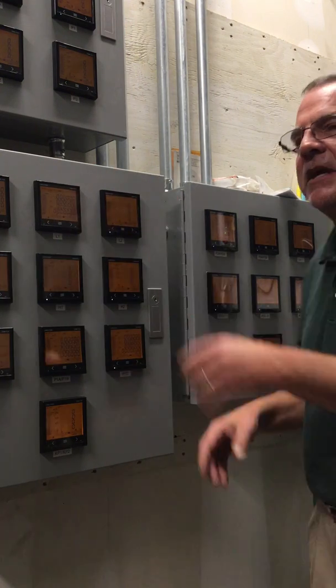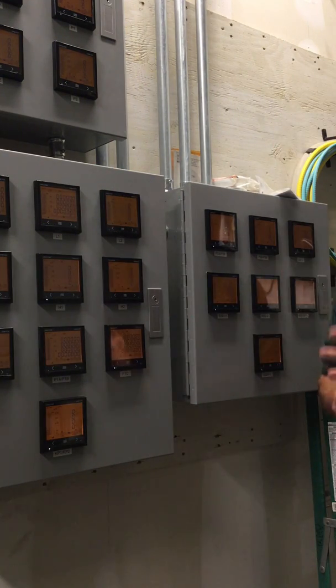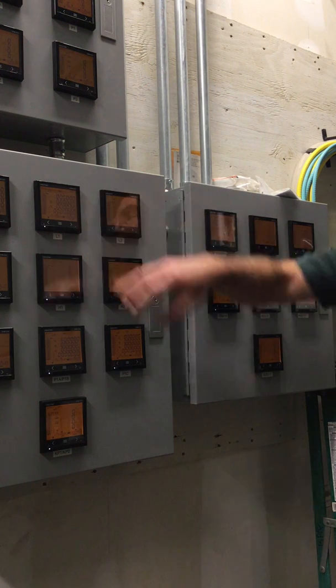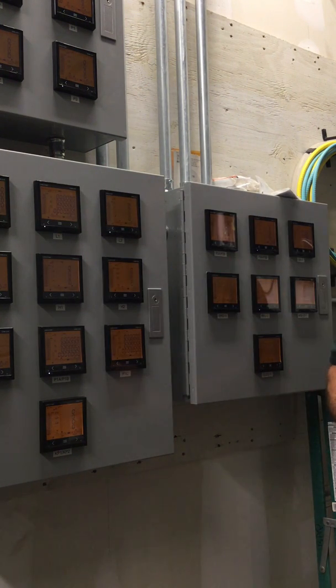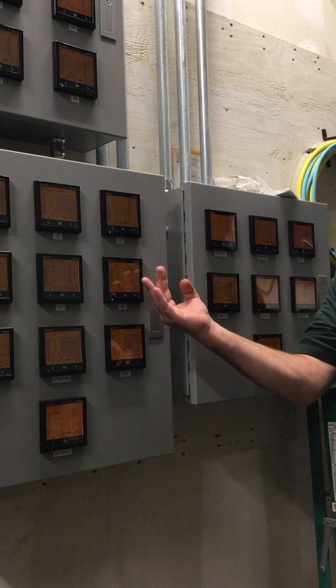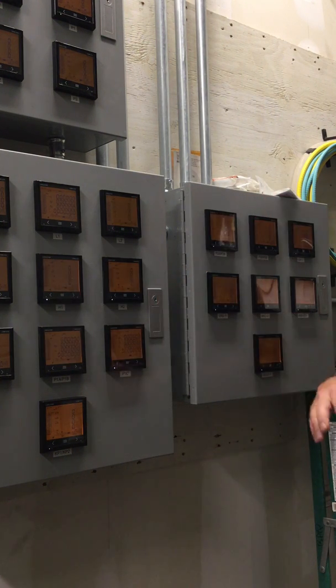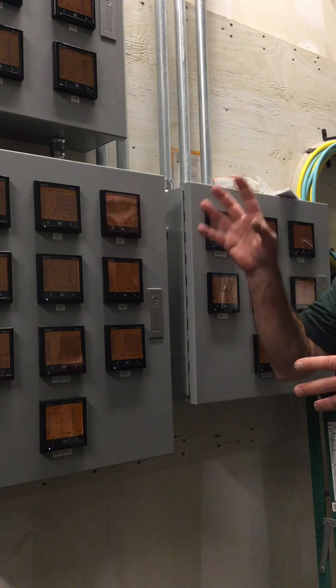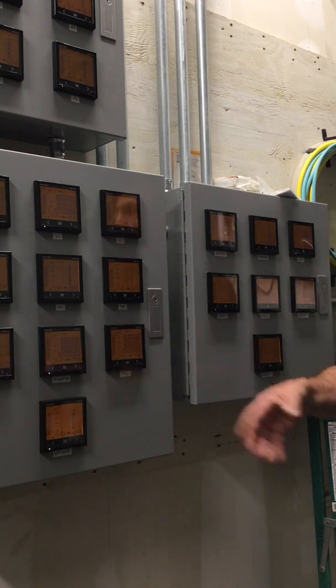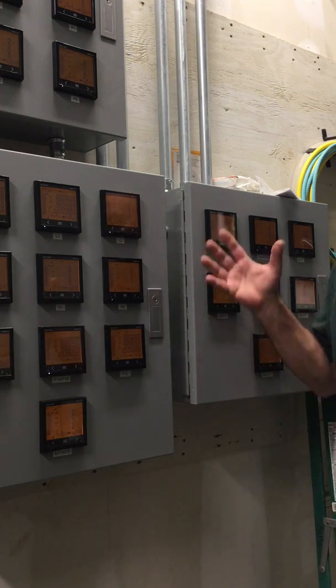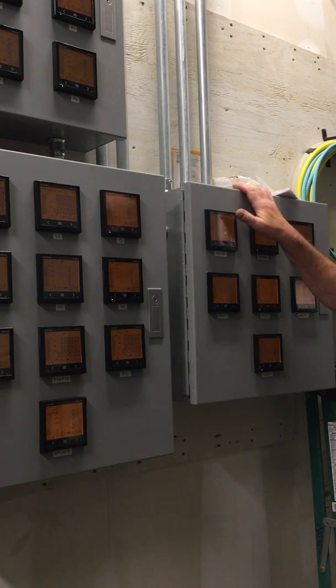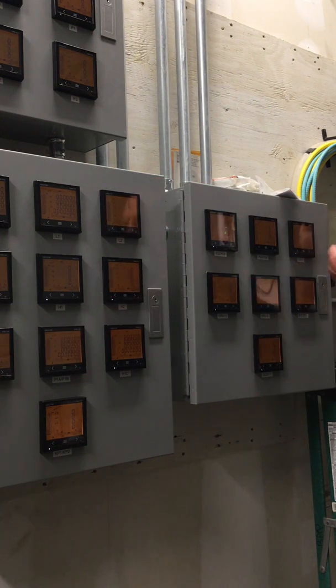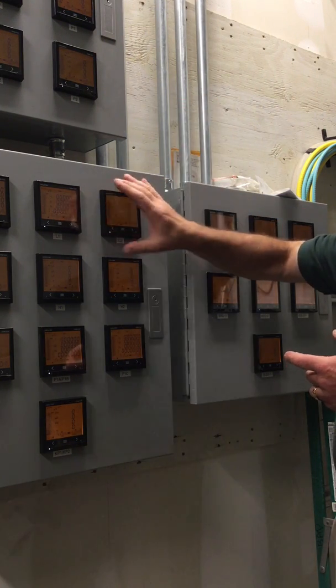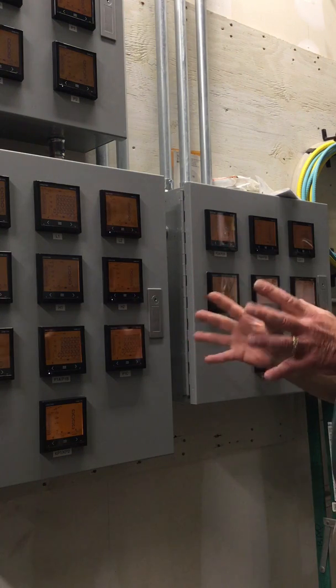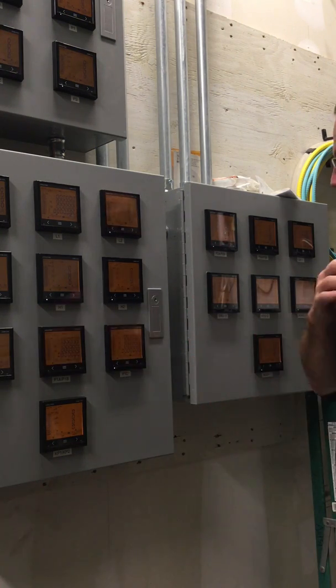But what we have to the meters is a feed to the meters from the auxiliary power supply to turn the puppies on. And we bring 3 phases to the bottom for measuring circuits, neutral if it's available, if not, okay. And then 3 current transformers. In as much as Ohm's law is a given, it's called Blondel's theorem. That's also a law. Volts times amps off the same phase equals VA, you throw in some power factor and you have watts. So whether it's this meter or any other meter that's out there, we all work with Ohm's law and Blondel's theorem. End of story.